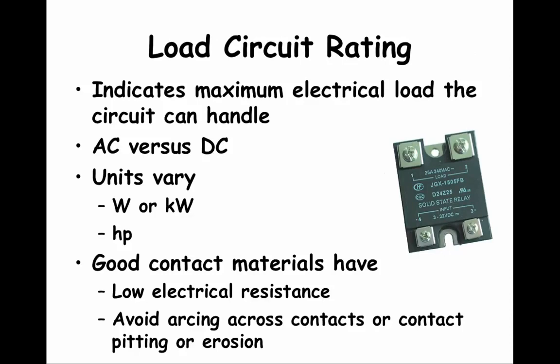The final characteristic is the load circuit rating, which tells you the type and maximum electrical load that the relay can handle. Some relays can only control alternating current devices and others only direct current powered devices. The load side will usually give the maximum kilowatts or horsepower that can be controlled by the relay. Finally, for electromechanical relays, the contact materials need to have low electrical resistance, avoid arcing when disengaged, and should not pit or erode when they open and close.